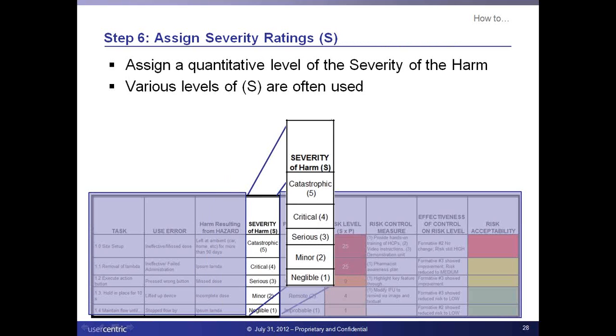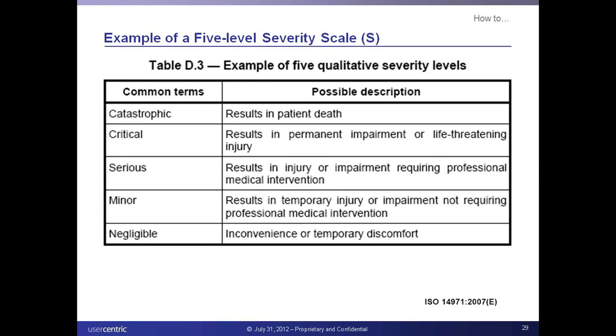Following the identification of a hazard, you want to understand what the severity is. So what you want to do is assign a level of severity. As you can see in this example, there's catastrophic to critical, all the way down to negligible. There are lots of ways to do this. Here's an ISO standard, 14971, and it's actually got an appendix called Annex D, which presents a table of qualitative severity levels. So you can go from catastrophic, which could result in patient death, to something that's negligible. This is a qualitative way of doing it, and you can assign a number to it. It's got five levels.